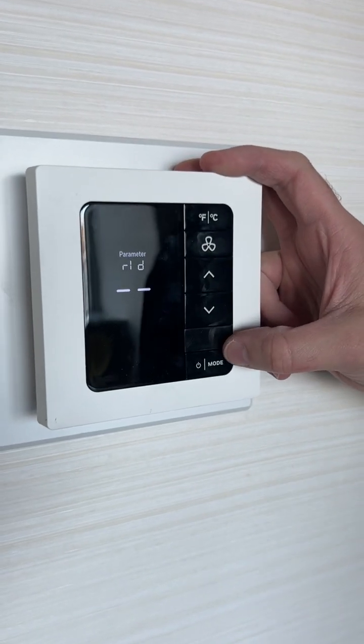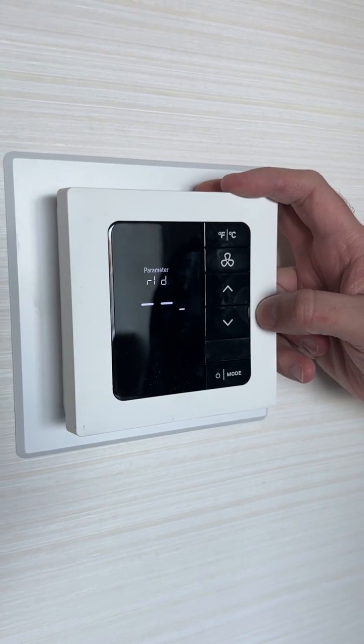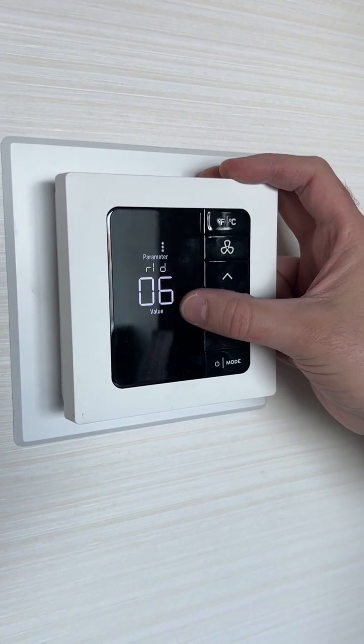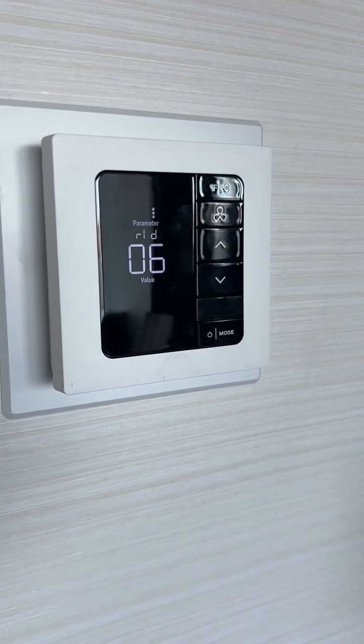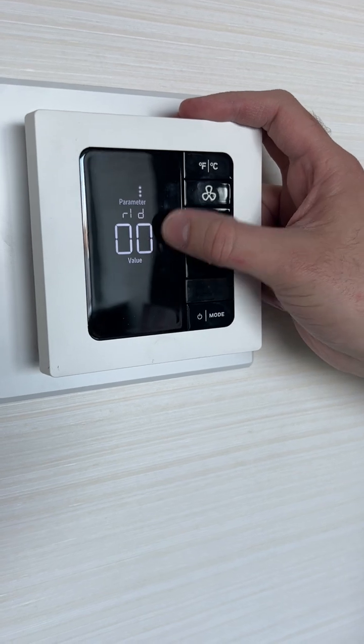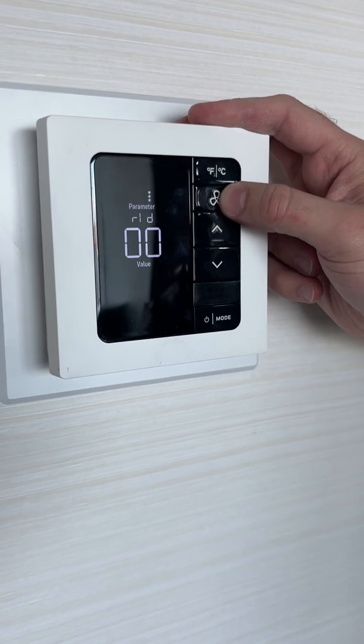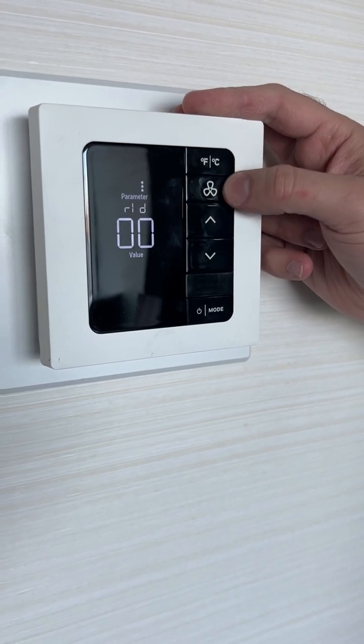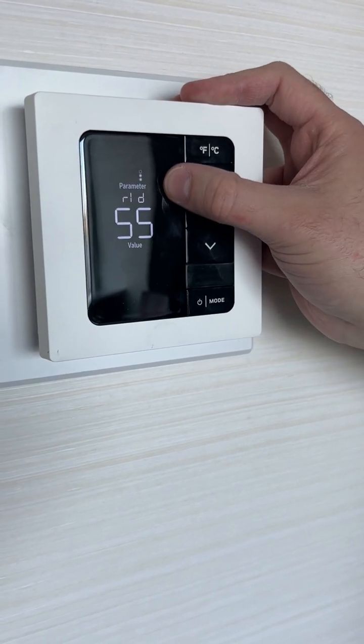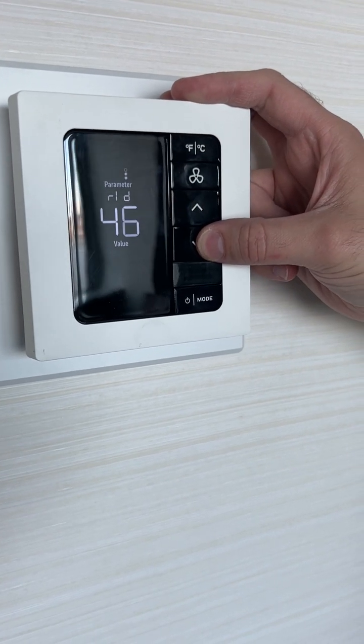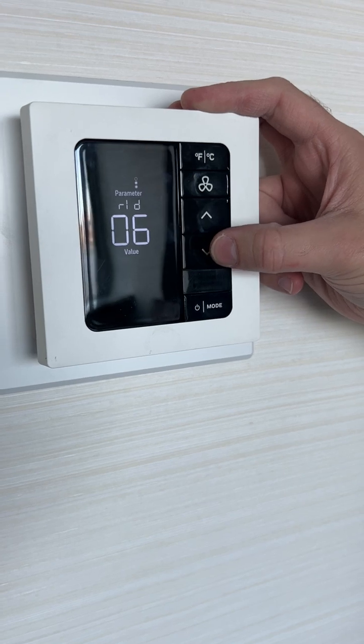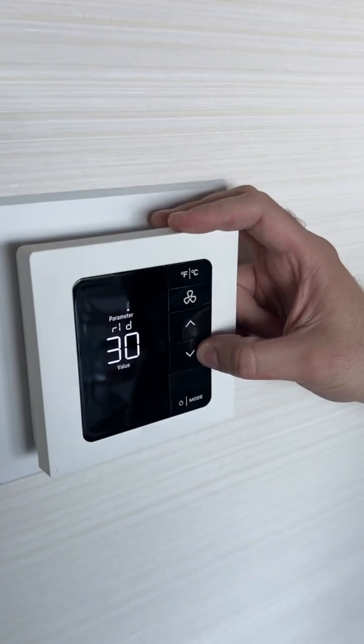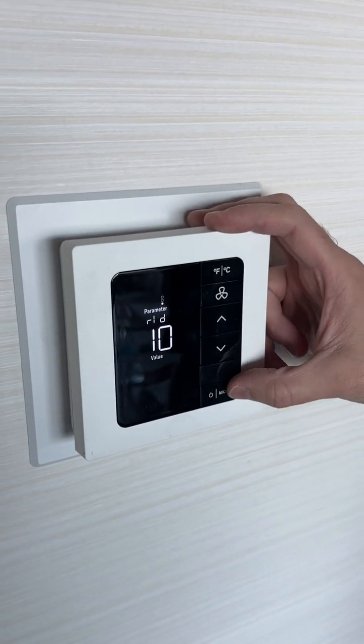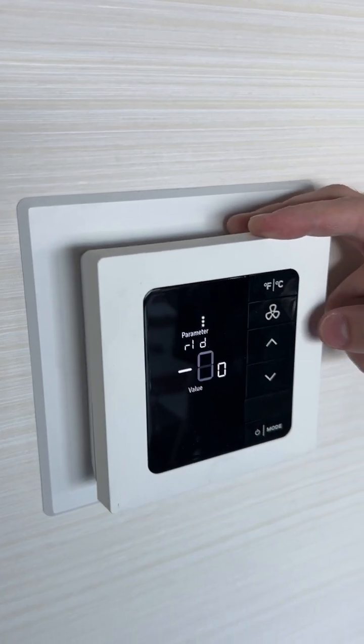First parameter we come to is RID, this is just what it boots up into. Default room ID is 65535, so I want to change that to the actual room number. High value is 0, because that's the primary, or only, HVAC zone of the room. Fan to go to the next, this is the medium value, the floor, so this is 3. Fan again, this is the low value, the room, so 310. Then fan again loops us back, and mode will save.